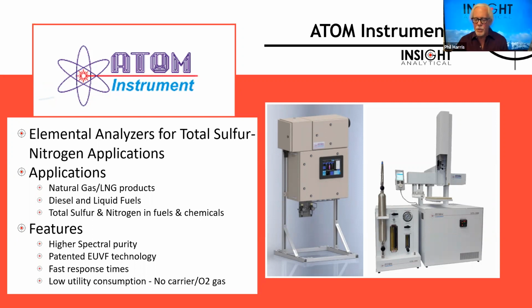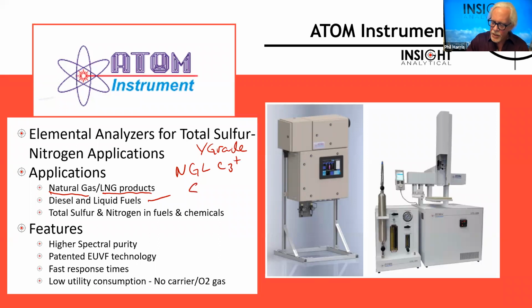And so we use this to do total sulfur in applications like total sulfur in natural gas, total sulfur in LNG, in diesels and other liquid fuels, so things like natural gas liquids, Y-grade, C3 plus streams, C5 plus streams. And so it allows us to do a measurement of total sulfur content. And of course, this is important to us because it's a specification on almost every hydrocarbon product that we sell. Whether it's natural gas, whether it's propane, butane, gasoline, there's a specification on total sulfur. And so we use this to do those measurements to make sure we can meet that specification.